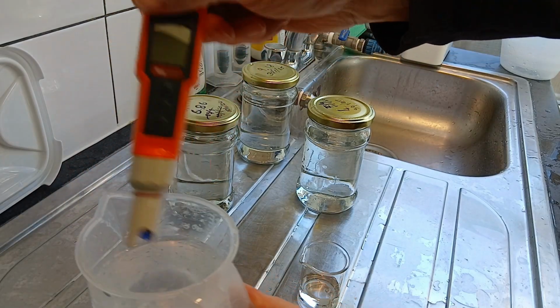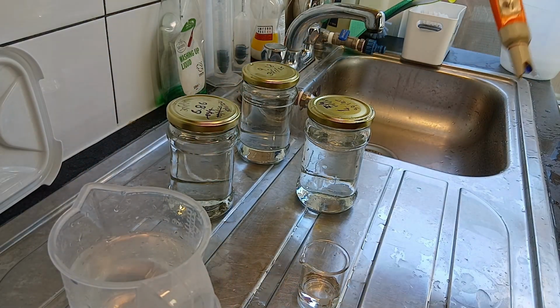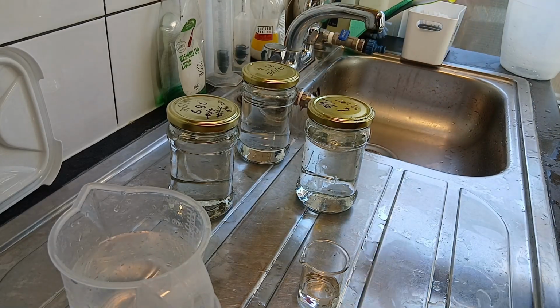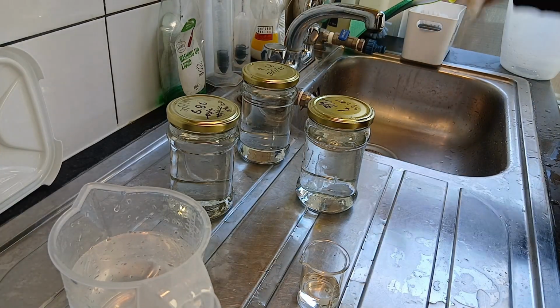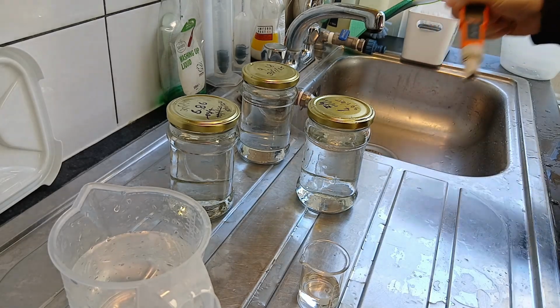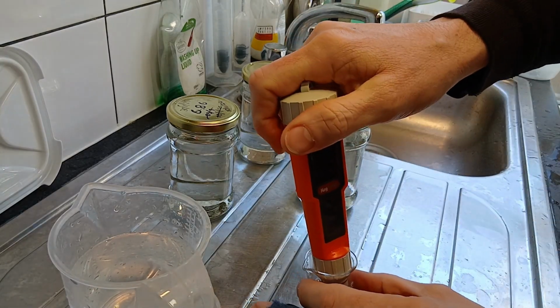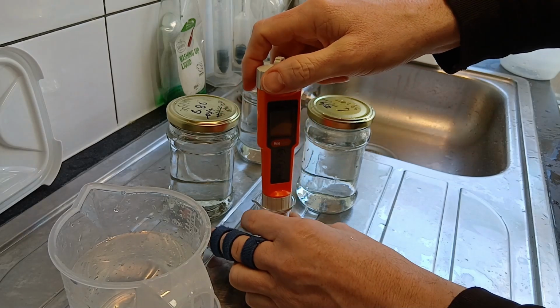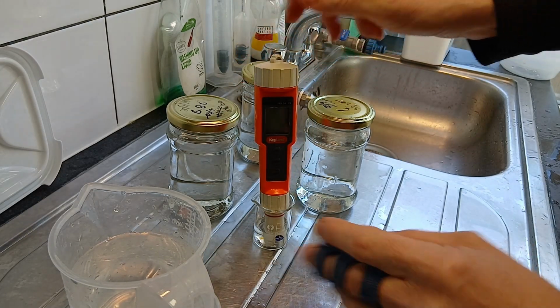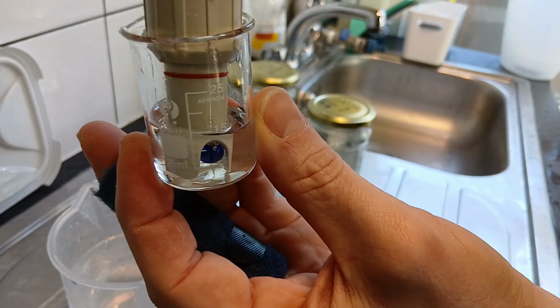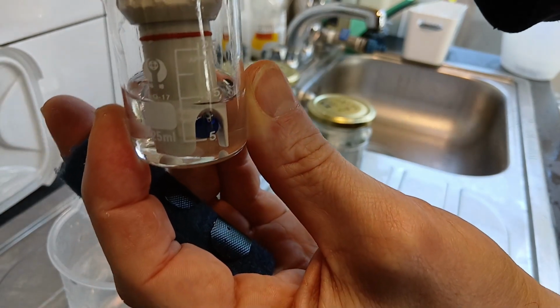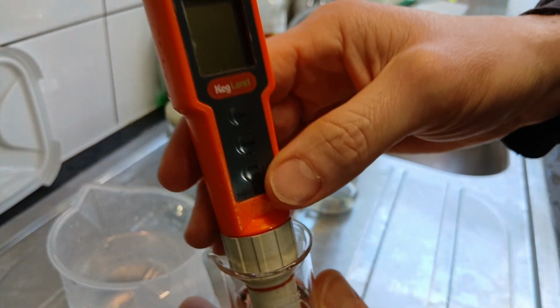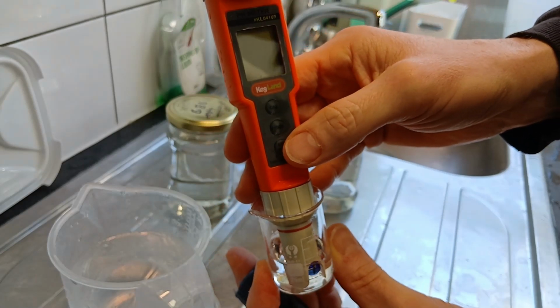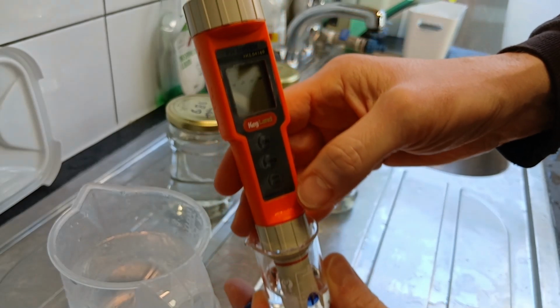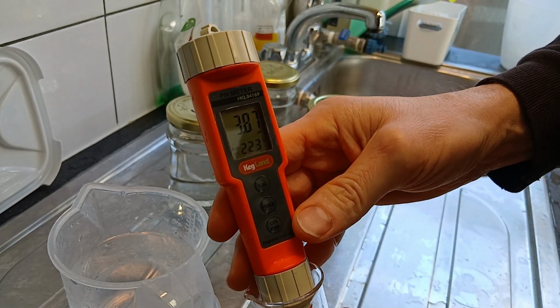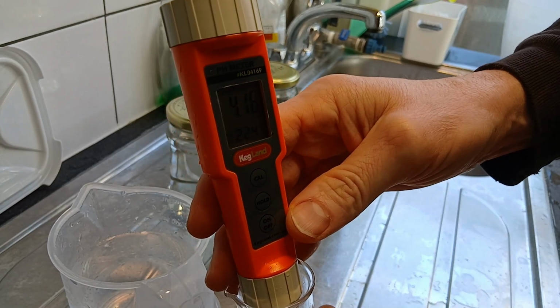So pH probe, just going to shake off any residual water on there. Try not to smack the probe on the sink, and then we'll get it into the solution. Now you can see there the probe. I'll bring it up to the camera. The probe is fully submerged in the buffer solution. Now I've always been told don't turn the pH meter on until it is in a liquid. So we'll turn that on and let's see, can we see the reading?